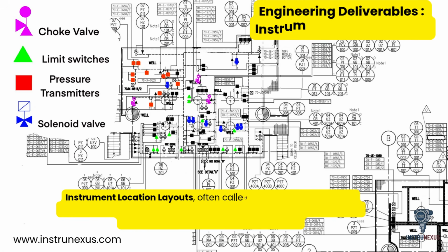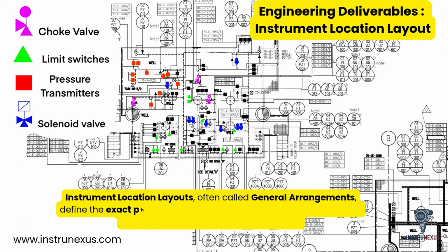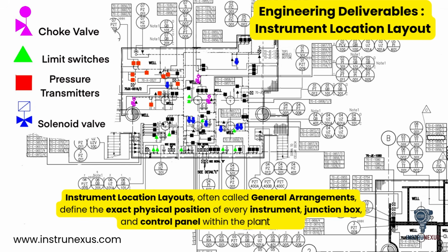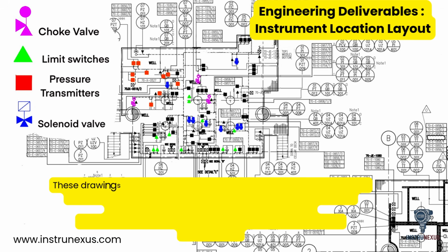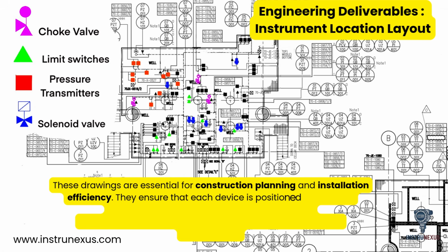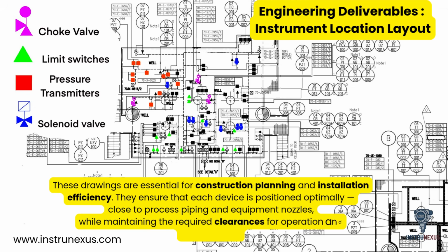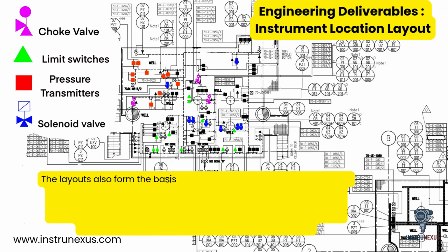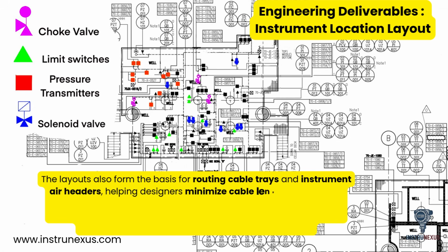Instrument location layouts, often called general arrangements, define the exact physical position of every instrument, junction box, and control panel within the plant layout. These drawings are essential for construction planning and installation efficiency. They ensure that each device is positioned optimally, close to process piping and equipment nozzles, while maintaining the required clearances for operation and maintenance. The layouts also form the basis for routing cable trays and instrument air headers, helping designers minimize cable lengths and reduce overall construction costs.